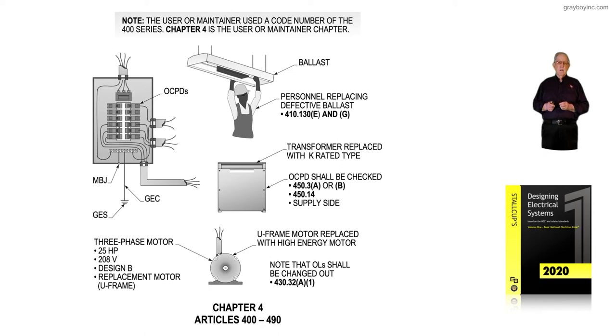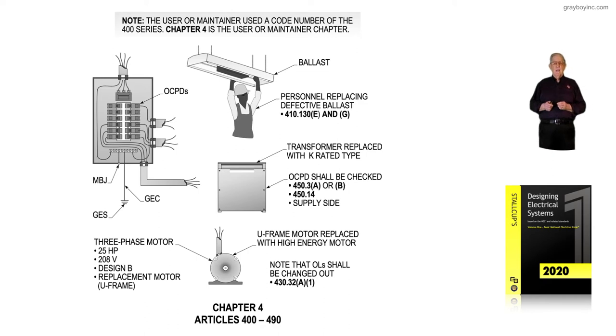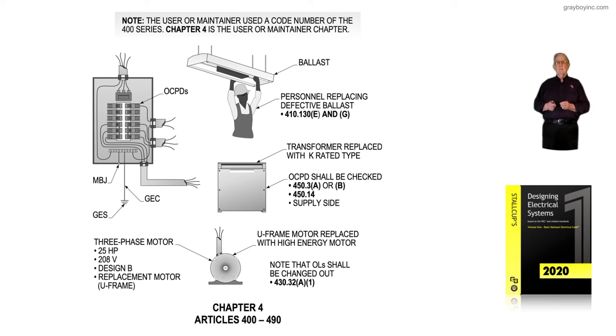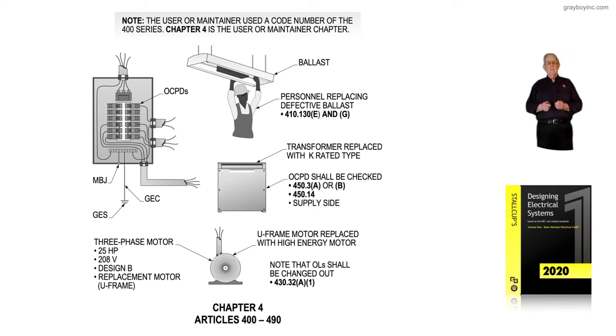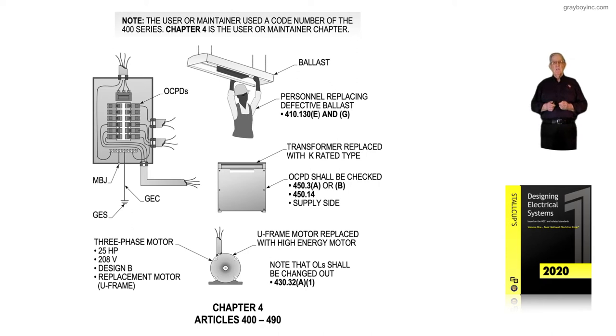The overcurrent device shall be checked — if it's a transformer — by 450.3A or B, and 450.14 for the disconnect and the supply side. Notice the transformer is replaced with a K-rated type transformer, meaning that's usually for computer systems and sensitive electronic equipment. Since it's a replacement, we'd go to Article 450 to handle that.